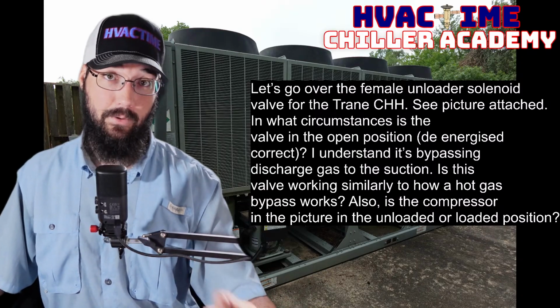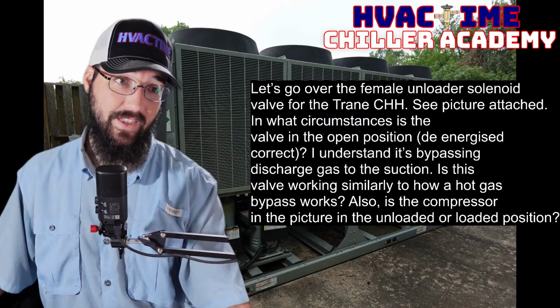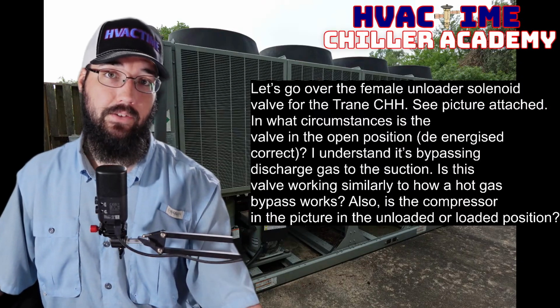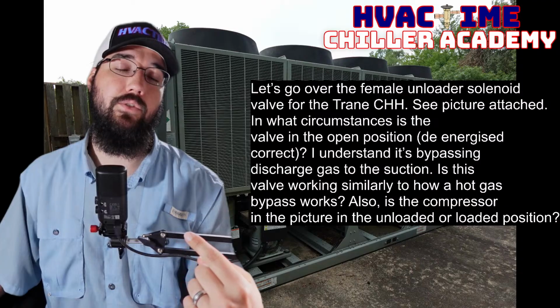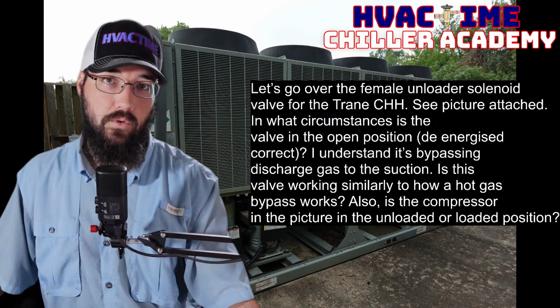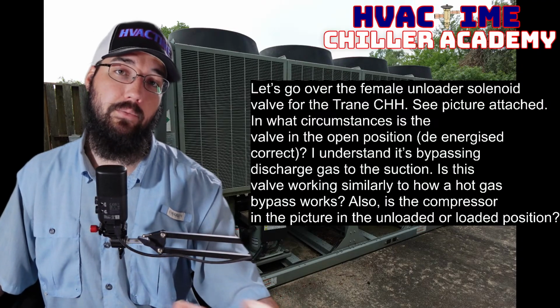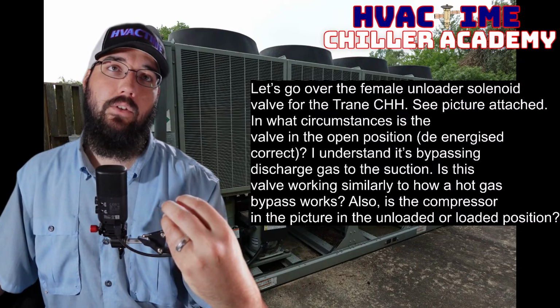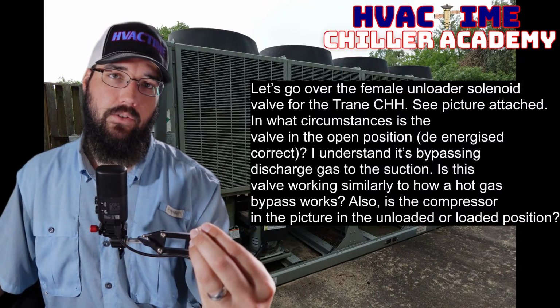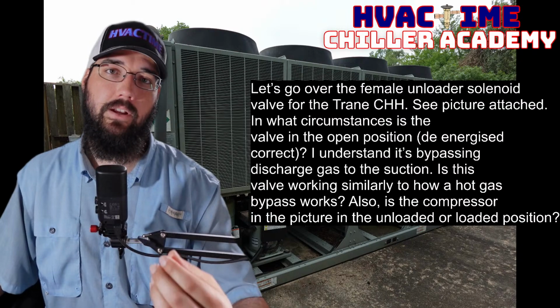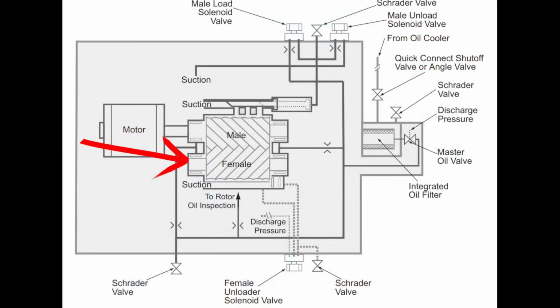be de-energized, allowing bypass. Then, after it gets past the startup phase, it will move into a normal mode, where we want the compressor to begin to load. Then we will energize the solenoid for the female unloader, and when that gets energized, it does block off the bypass internally on the compressor.